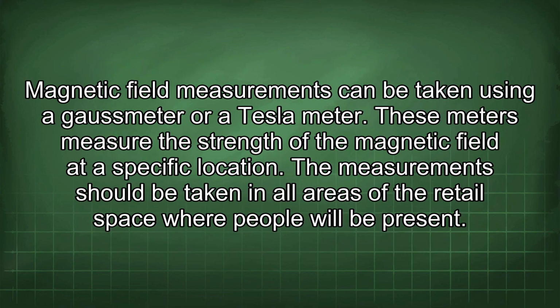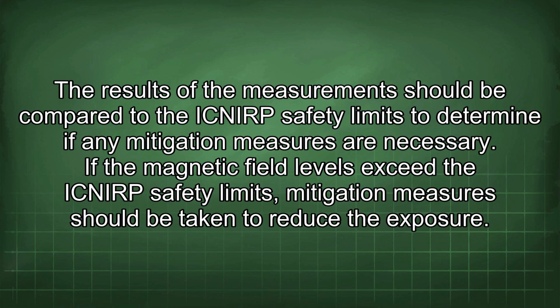Magnetic field measurements can be taken using a Gauss meter or a Tesla meter. These meters measure the strength of the magnetic field at a specific location. The measurement should be taken in all areas of the retail space where people will be present. The results of the measurement should be compared to the ICNIRP safety limits to determine if any mitigation measures are necessary. If the magnetic field levels exceed the ICNIRP safety limits, mitigation measures should be taken to reduce the exposure.